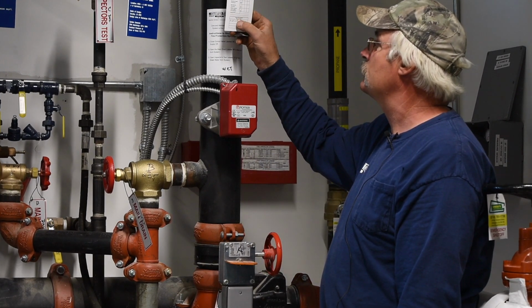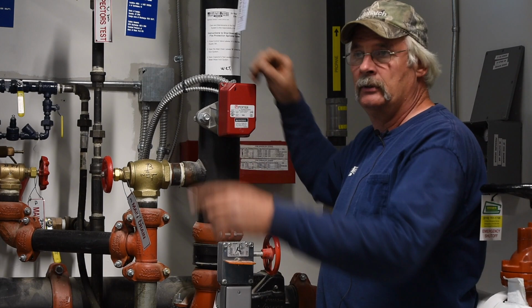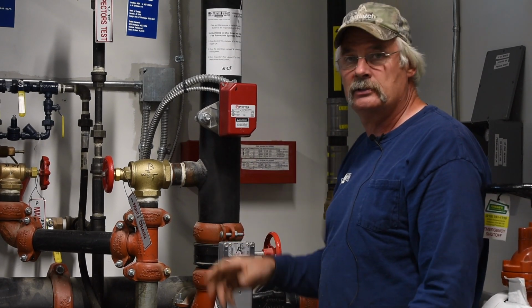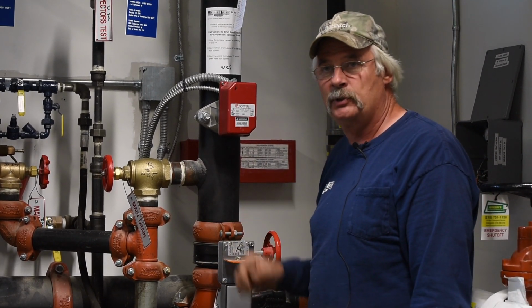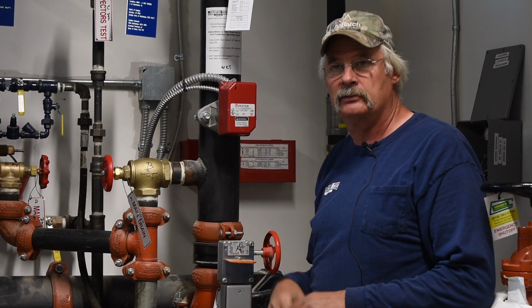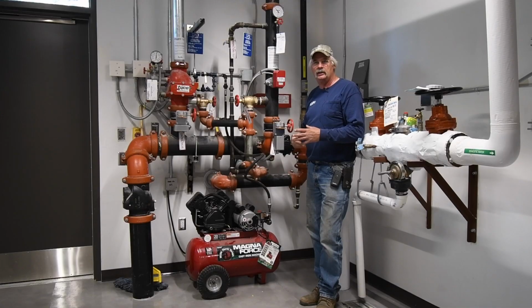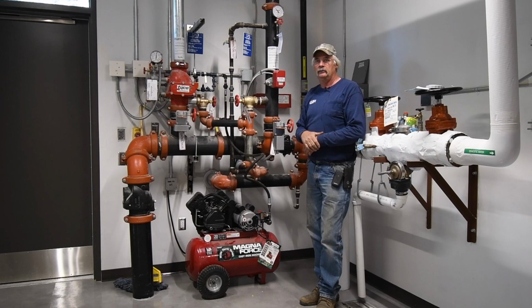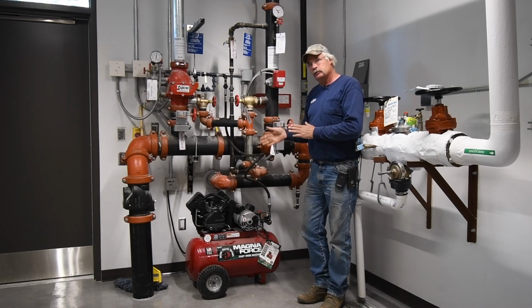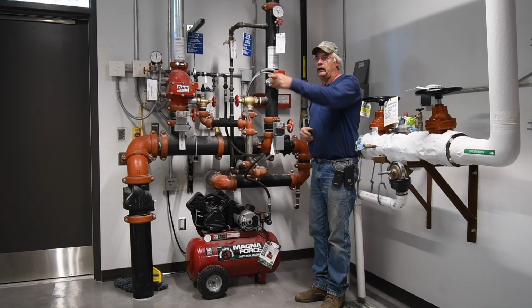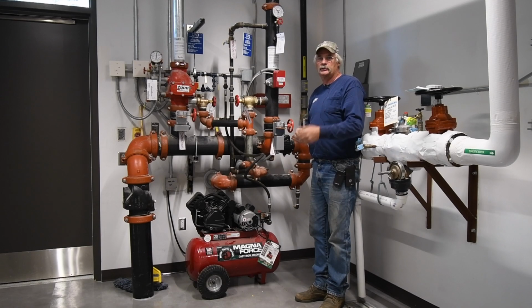We've had all the systems checked and tagged, and made sure all the different flow switches and drains and tamper switches and PIV switches and fire pump running and fire pump loss all come into your panel. All your PIVs have been checked. So if somebody goes to shut one, it'll automatically trigger the panel, which will call in, and I'm sure the maintenance contact is on that list of people that are notified immediately.